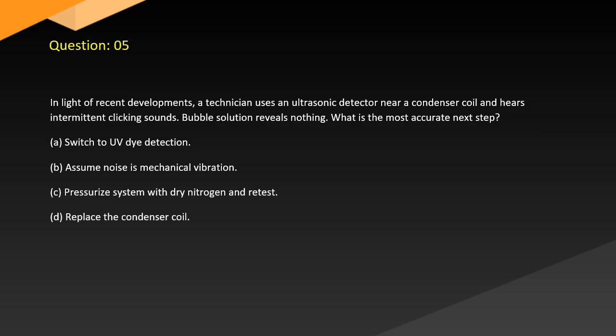Question 5. In light of recent developments, a technician uses an ultrasonic detector near a condenser coil and hears intermittent clicking sounds. Bubble solution reveals nothing. What is the most accurate next step? A. Switch to UV dye detection. B. Assume noise is mechanical vibration. C. Pressurize system with dry nitrogen and retest. D. Replace the condenser coil.